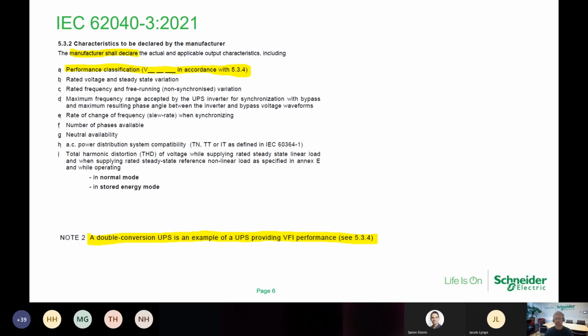If we take a look at the IEC 62040-3 test performance standard, we can see in clause 5.3.2 that the manufacturer shall declare, at point A, the performance classification according to clause 5.3.4. And we can see at the bottom that if it is a double conversion UPS, it is classified as VFI performance. The UPS we develop today are double conversion, so VFI performance.